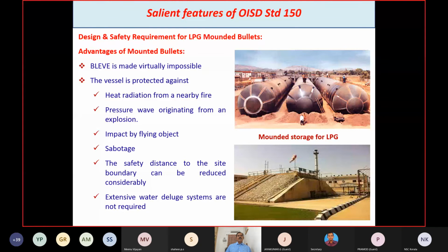Immediately 30 to 40% of the liquid will flash outside and mix with an equal amount of air, entrained as a mist. Since fire is already there outside, the vapor mist will catch fire, resulting in a very big fireball. The fireball will be mushroom shaped and will last only a few seconds, but its effects are highly devastating. The burning rate will be 1 ton per second. Just imagine: it will release tremendous energy, several kilowatts per square meter. It will also cause overpressure effects, and parts of the bullet will be thrown a great distance, causing secondary fires and other damage. So the boiling liquid expanding vapor cloud explosion is the most dangerous, worst fire as far as LPG is concerned.